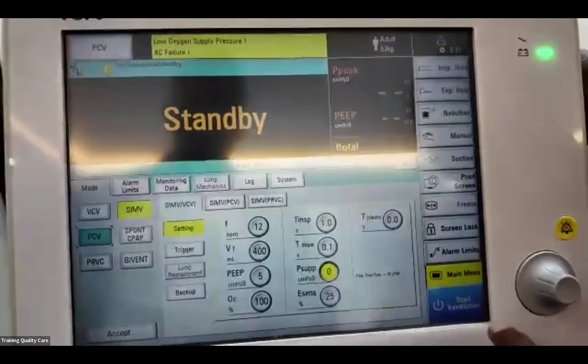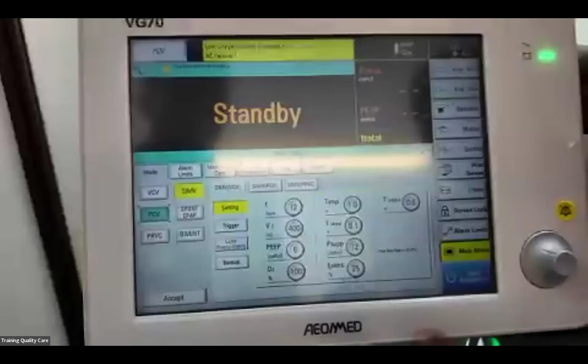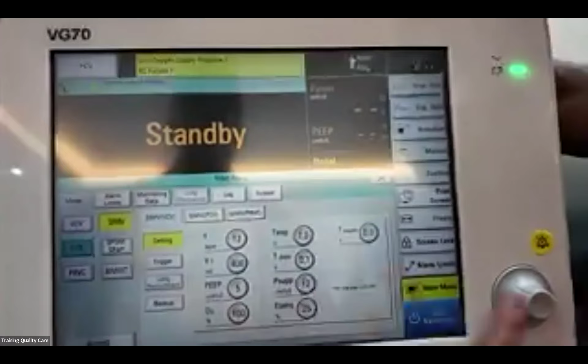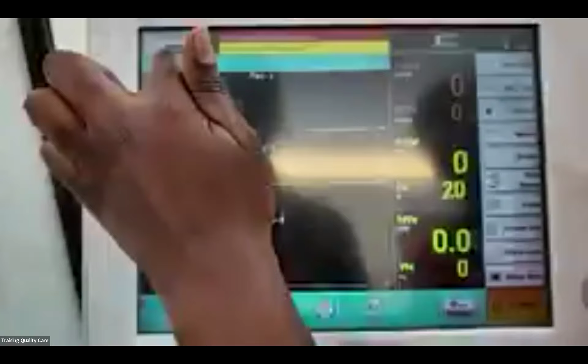Give a little support. So I'm going to do the pressure support. And that is add some pressure support. Maybe I can give 10 or 12. And this means in case the patient decides to breathe on themselves, when they initiate the breath, I'm going to give 12 centimeters. Other things is the time to inspire. And then after that, I can accept and start. So I've just started ventilating on SIMV plus the pressure support. So in case the patient decides to breathe on themselves, they are supported by the ventilator with some pressure support.